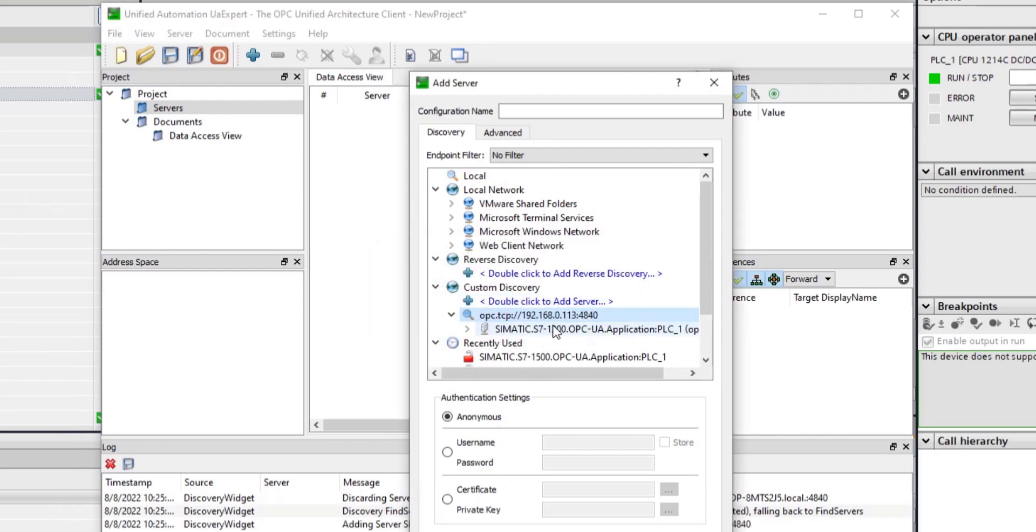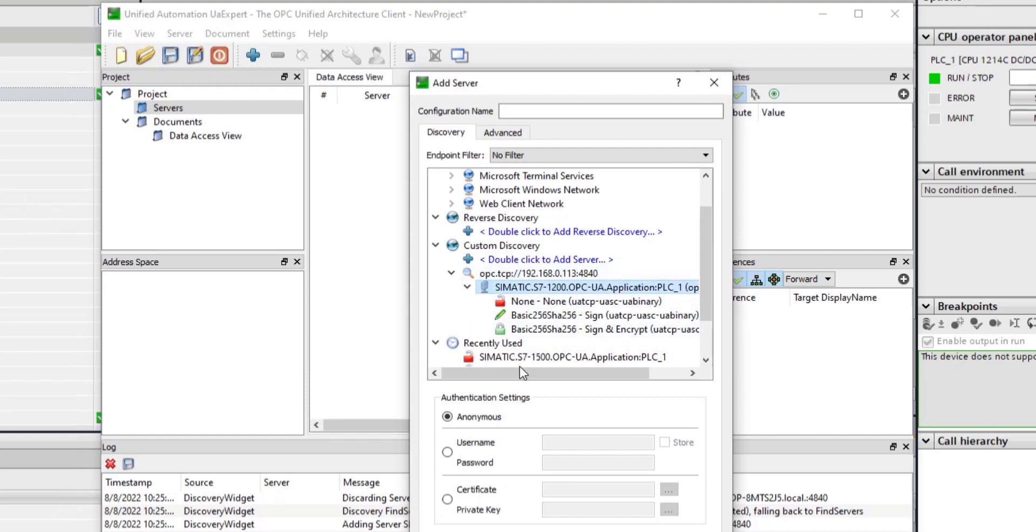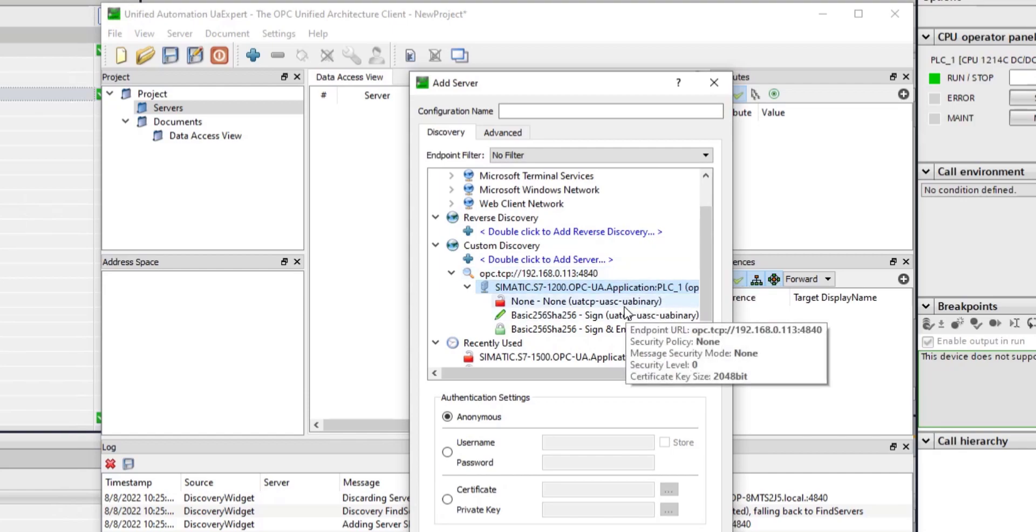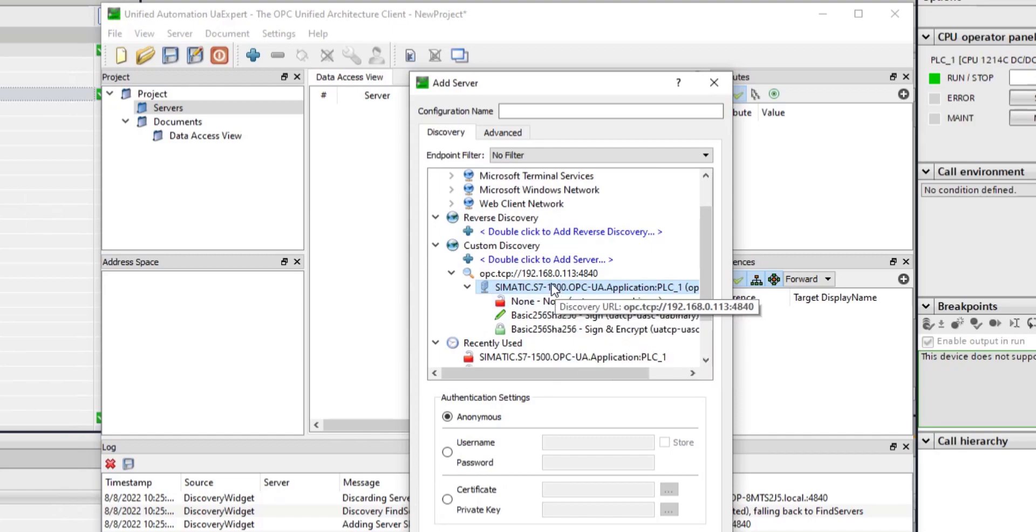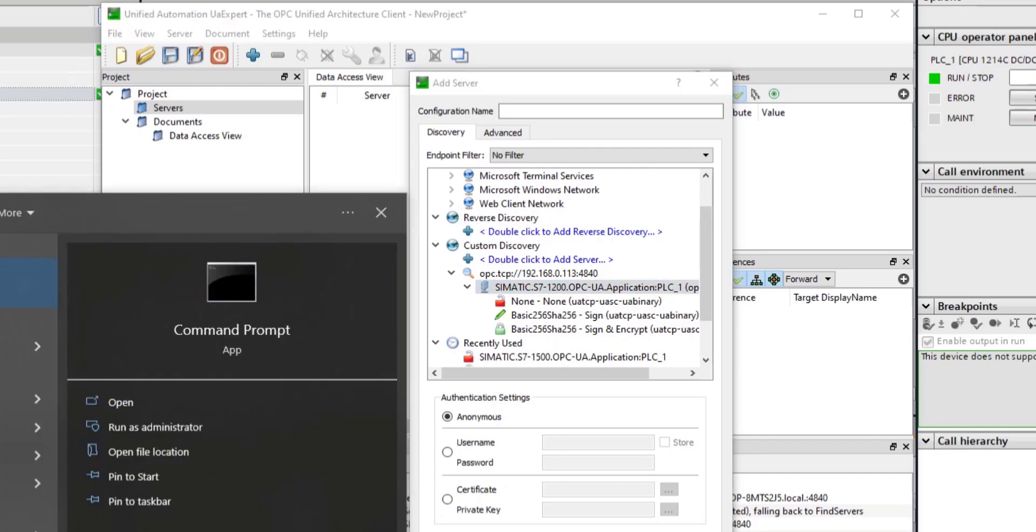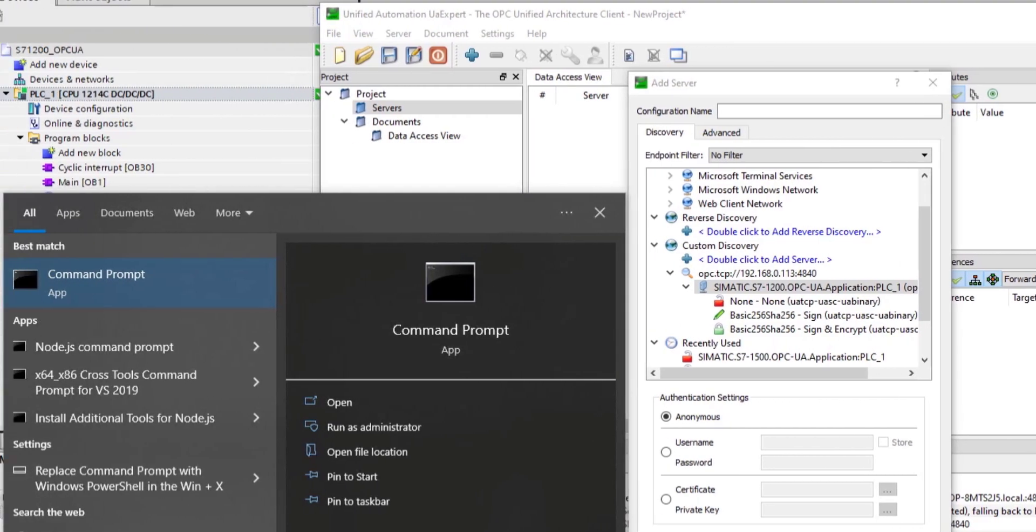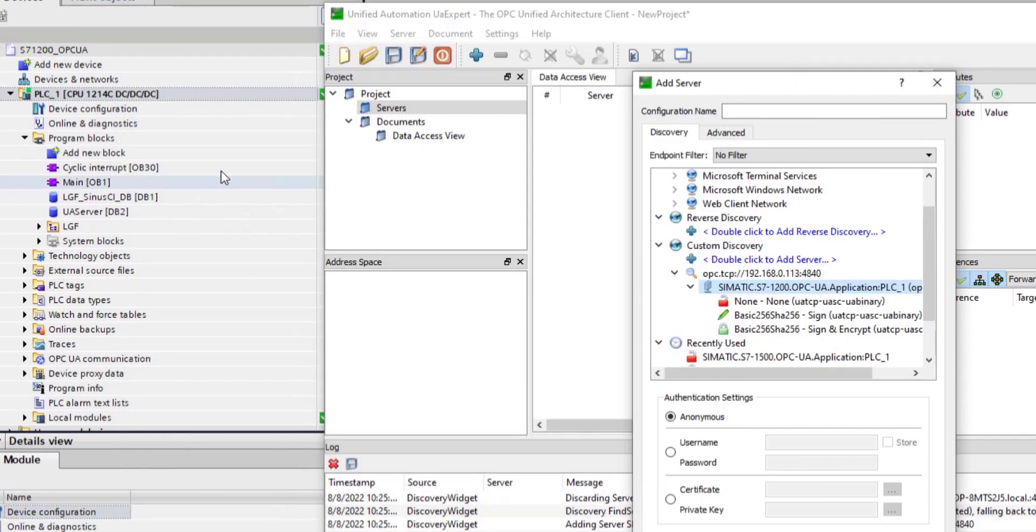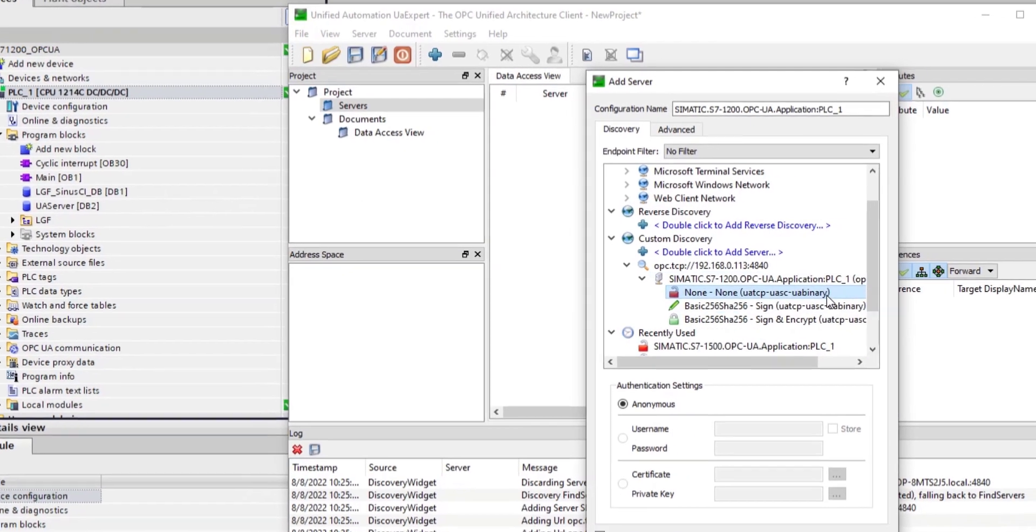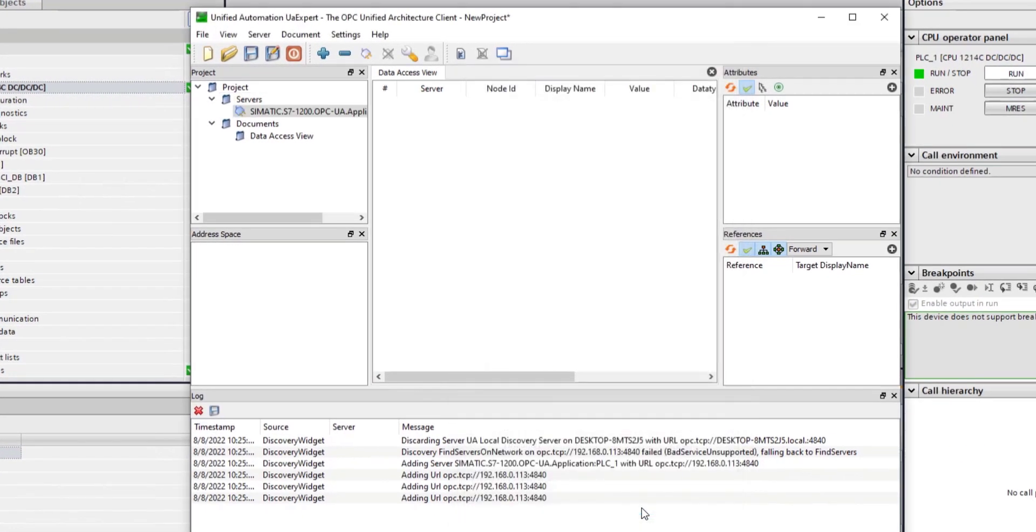And now let's go to UA Expert and connect with our server on 192.168.0.113 port 4840. It discovered the server. So this step now already tells us our OPC UA server is up and running. So this is very good news. If you're not getting this, either you haven't downloaded to the PLC or you don't have connectivity. Connectivity, you should be able to test by just pinging. So if we did CMD and then ping 192.168.0.113. If you're not getting any reply here, then it will be down to your network. If you are, then probably you have not downloaded the config. I would urge you to recompile and download the configuration.